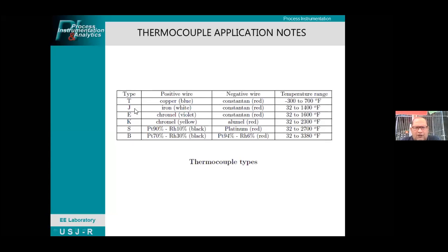For the type J thermocouple, where the positive wire is the iron metal, that should be white, and constantan will be red. Now take note that all the negative wires of different metals are colored red. So that will be a standard for these thermocouple applications. Okay, then also for this type J, temperature ranging from 32 to 1,400 degrees Fahrenheit.